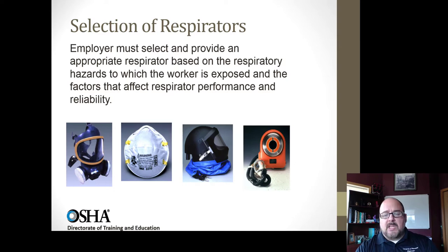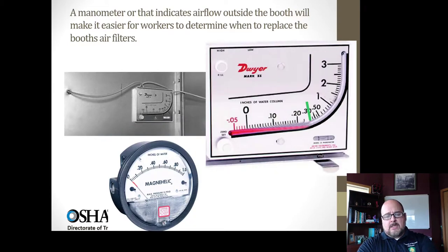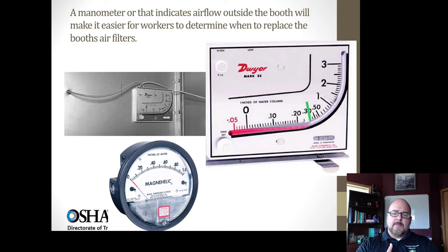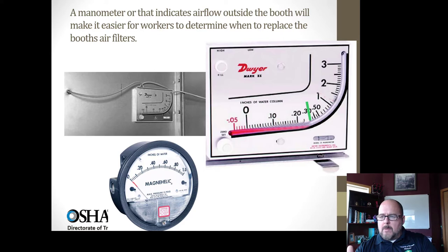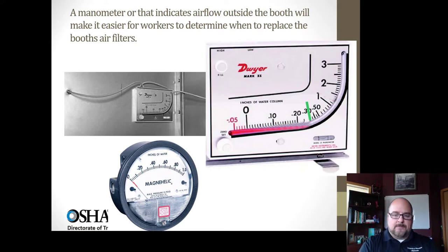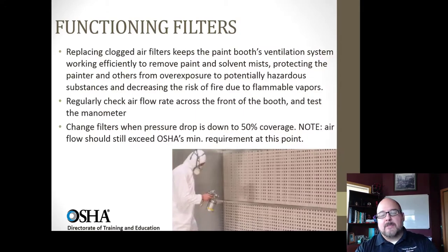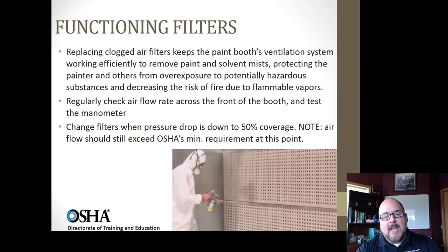You may need to choose respirators because some flammable liquids are also hazardous to health — look at the SDS to see what is required. Every spray booth should have some form of pressure differential device indicating how used or filled the filter bed is. A magnehelic gauge or a water manometer are common options. Green typically means the filter bed is fresh; red means it's time to change it. When I used to inspect spray booths, the manometer was usually broken. We'll talk more about when to change filters in the next lecture.